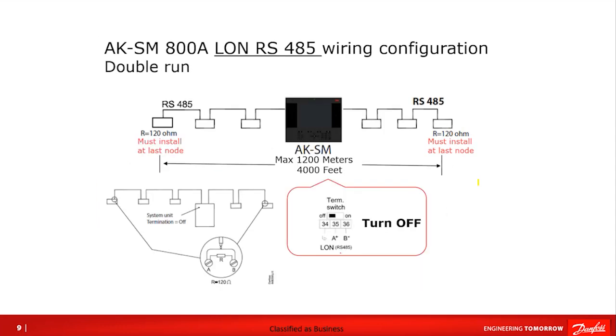You can also configure a layout where the System Manager is in the middle of the loop. In this case, because the System Manager is not one end, the termination switch inside the unit would be in the off position. The System Manager would then go in two directions with the communication wiring, and each end would need termination with a 120-ohm resistor at the devices on either end.